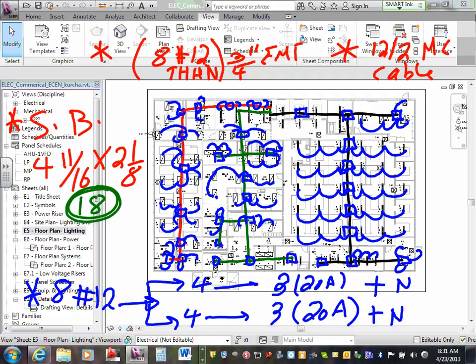So 8 conductors, all of them number 12, in an EMT conduit. By the way, EMT conduit, 3/4 of an inch, you can load it up to 16 by code, but you don't want to go all the way up to 16 for future expansion. So if you walk into a building with 8 number 12s, knowing that if you need to add, you still can add up to 16. If there is a ninth, pull another conductor. But ideally, if you walk in with 8 number 12s, that allows for future expansion. So that's the assembly that I'm using to take off this project.